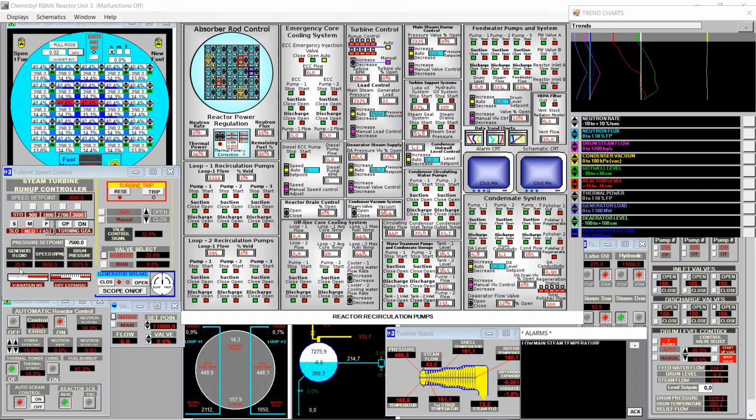The oscillation is quite huge. It went up to 100 megawatts and down to 12. Okay. So now I will slowly reduce a bit the power set point, maybe to 13. And it doesn't seem it will go above 80 megawatts again. It seems it just stabilized around 30.